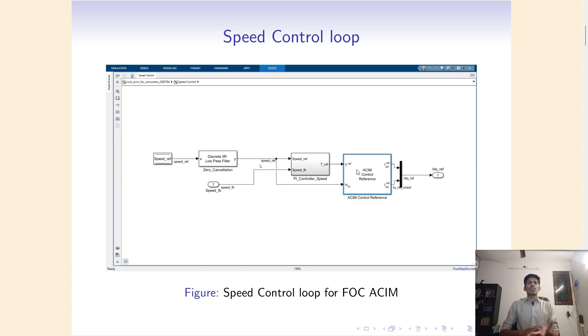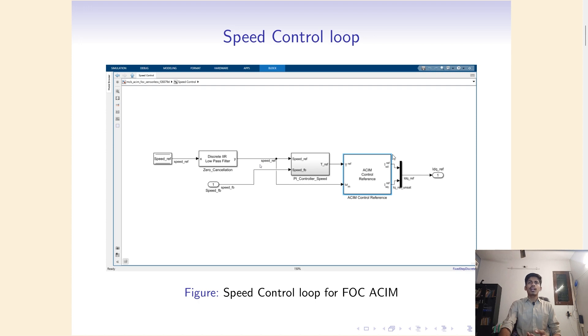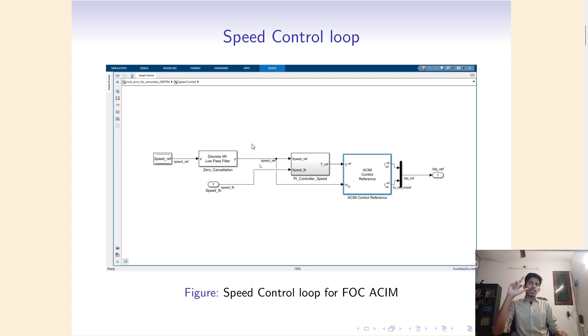This block takes those two parameters along with various induction motor parameters like inductance, maximum current, and rated flux. From all these parameters it generates isd and isq — isd stands for I-stator direct axis reference current, and isq stands for I-stator quadrature axis reference current. These two currents are given to the current control subsystem.